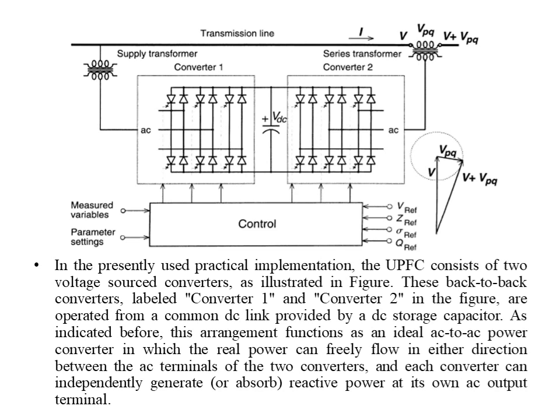So there are two converters connected back to back. Each converter itself absorbs and generates the reactive power required in the system. These two converters are connected by a common DC link which acts as an energy storage device. Control signals must be generated for both converters to operate so as to supply or inject reactive power to the system or absorb reactive power from the system.